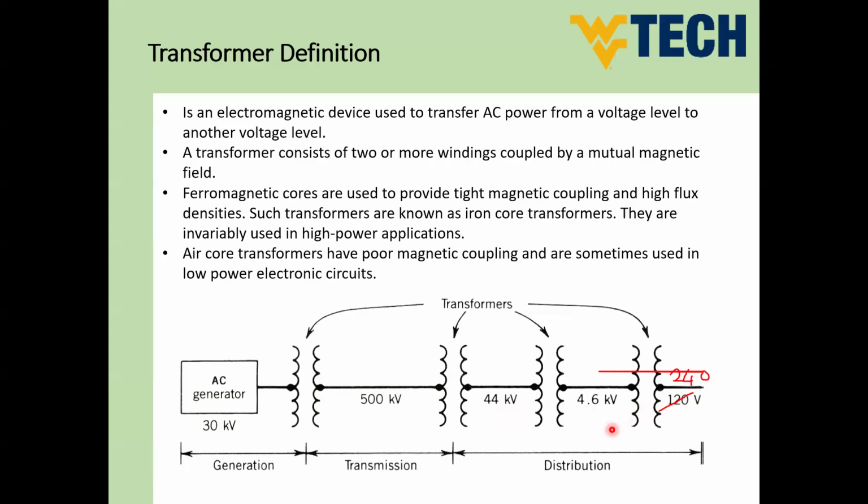If you have a factory that takes several tens of megavolt ampere, so 50 megavolt ampere, for instance, this is huge power to be supplied from a transformer of 240 volt or 4.6 kilovolts. So we may need 44 kilovolt, or higher, 13 kilovolt, for instance, 13.8 kilovolt.